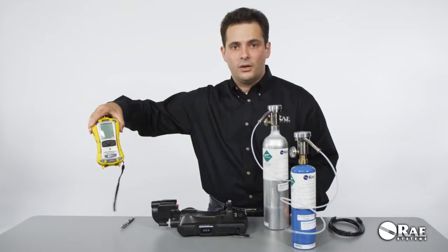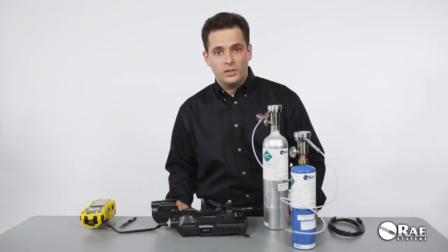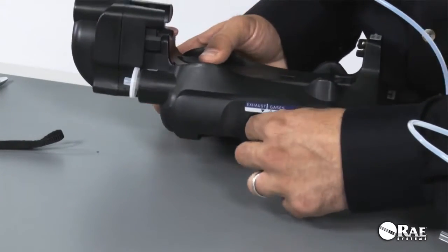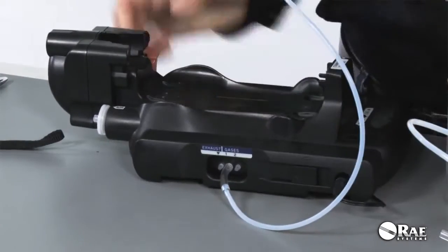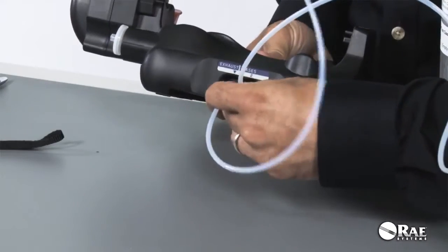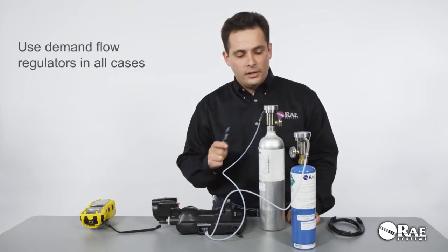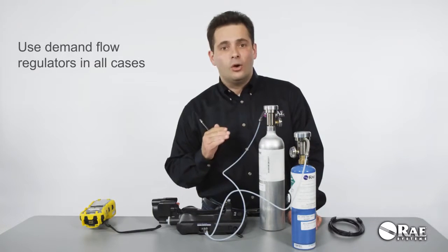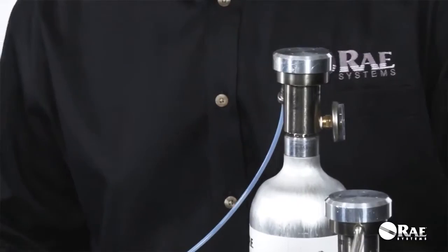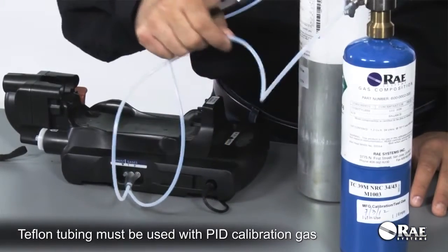For a standard configuration MultiRAE, I'm going to use the default inlet configuration. I'll connect the four-gas mix to the first inlet, and then connect isobutylene to the second inlet. Please note that demand flow regulators are required in all cases whenever you're using the AutoRAE 2, regardless of configuration. Whenever you use a gas to calibrate the PID sensor, Teflon tubing must be used with that gas.